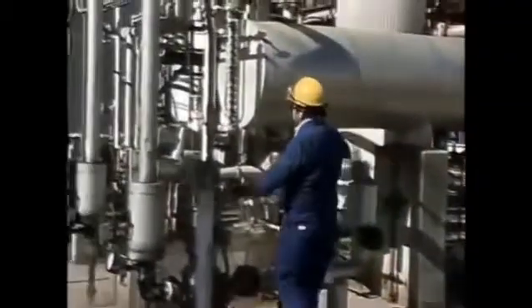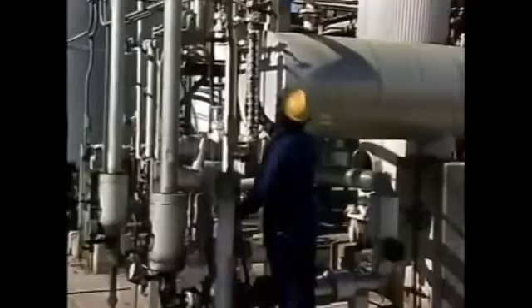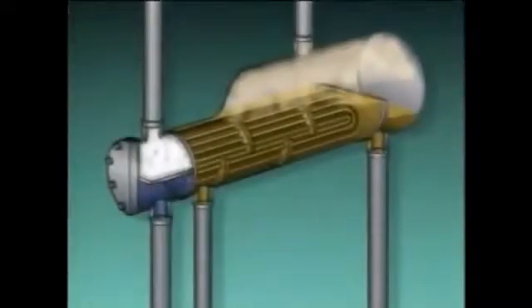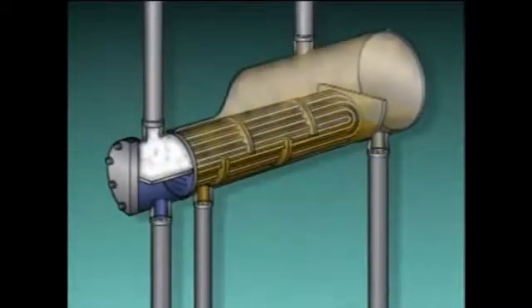One important check that should be made is the level in the reboiler. This check is made by observing the level in the reboiler's sight glass. The tubes in a reboiler must be covered with the process liquid. If the level in the reboiler drops too low, the tubes could overheat and be damaged. On the other hand, a level that is too high can be a problem, too.